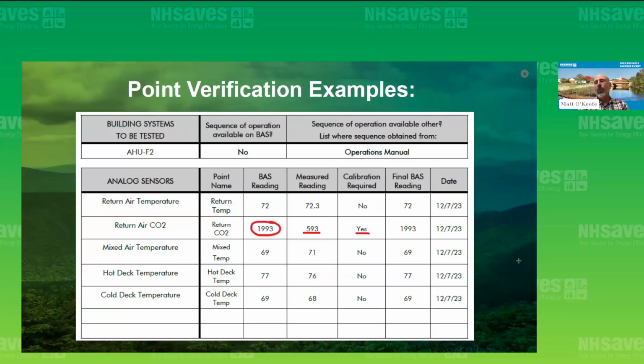So we'll go through some of the projects we've seen come through, where we're just looking at very high level major air handling systems and stuff that are typical findings. And one of the most common control sequences used out there is demand control ventilation, where it's using CO2 sensors in a space or return ductwork to tell the system how many people are in the area served by that air handling unit. So when the reading increases, the system brings in more fresh air that needs to be heated or cooled.